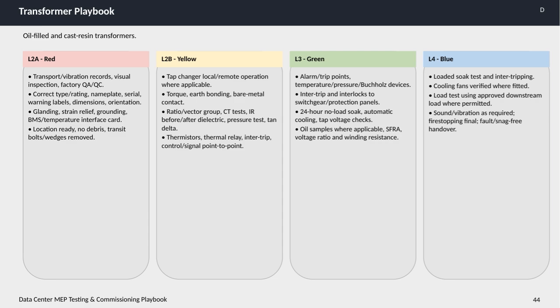Moving to level 2B, indicated by yellow, the focus shifts to functional and electrical checks. This includes testing tap changer operation both locally and remotely if applicable. Torque and earth bonding must be inspected, with attention to bare metal contacts. We verify ratio and vector groups, conduct CT tests, and perform insulation resistance tests before and after dielectric and pressure testing. Thermistors, thermal relays, and trips and all control and signal points are confirmed to be operating correctly on a point-to-point basis. Level 3, represented by green, emphasizes continuous monitoring and prolonged testing.